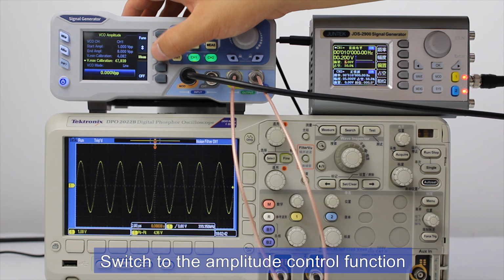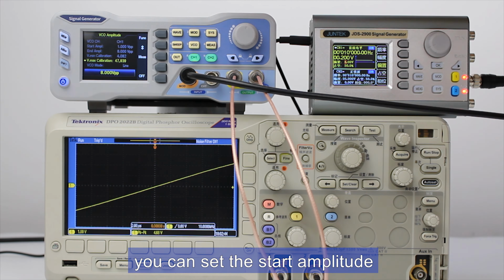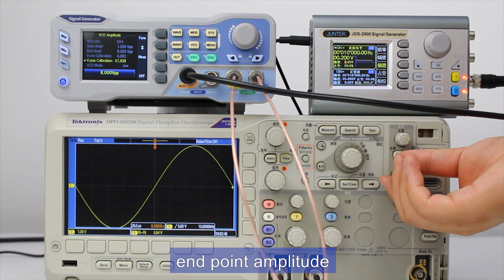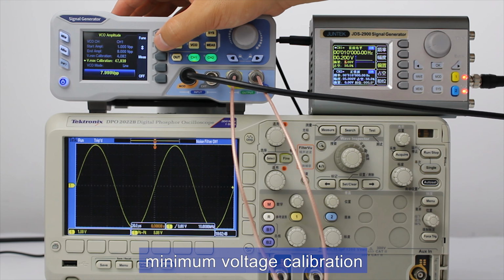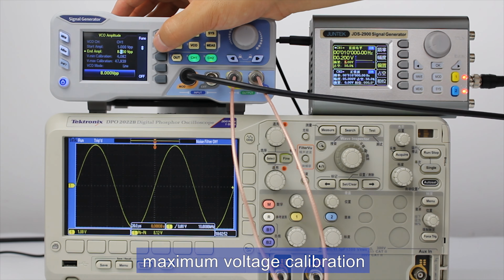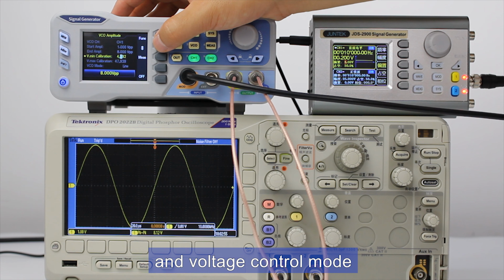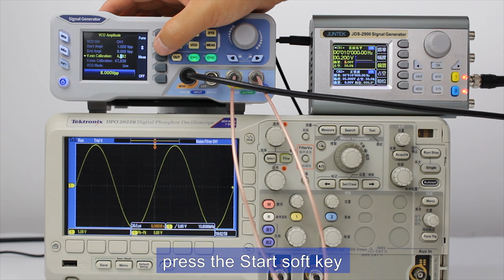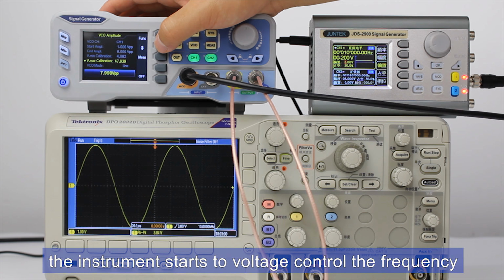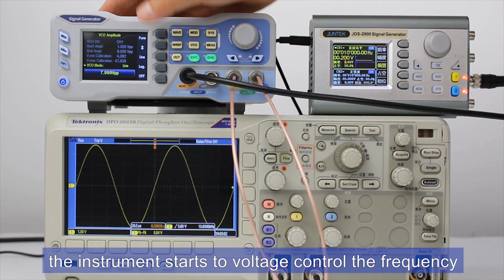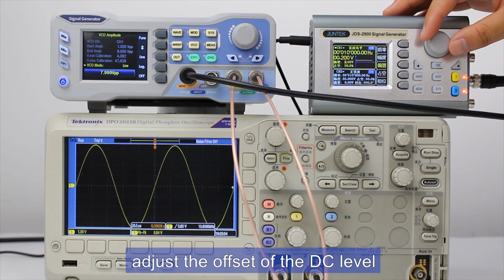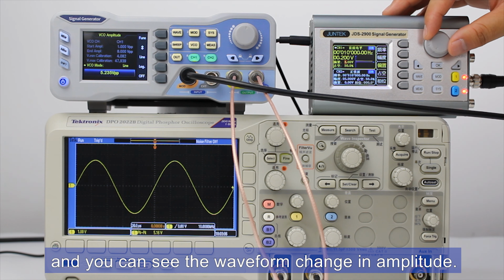Switch to the amplitude control function. You can set the start amplitude, endpoint amplitude, minimum voltage calibration, maximum voltage calibration, and voltage control mode. Press the start soft key. The instrument starts the voltage control. Adjust the offset of the DC level, and you can see the waveform change in amplitude.